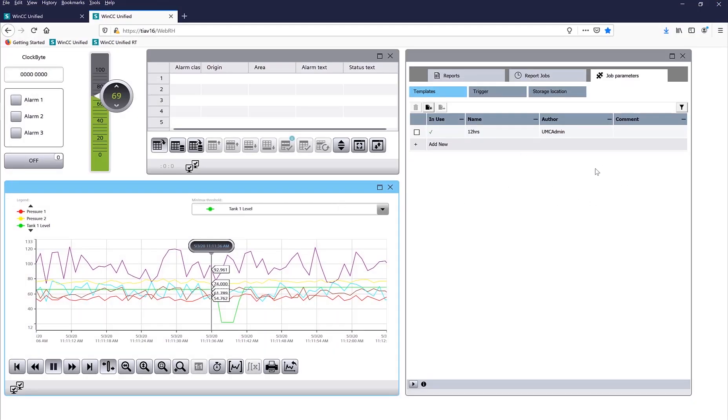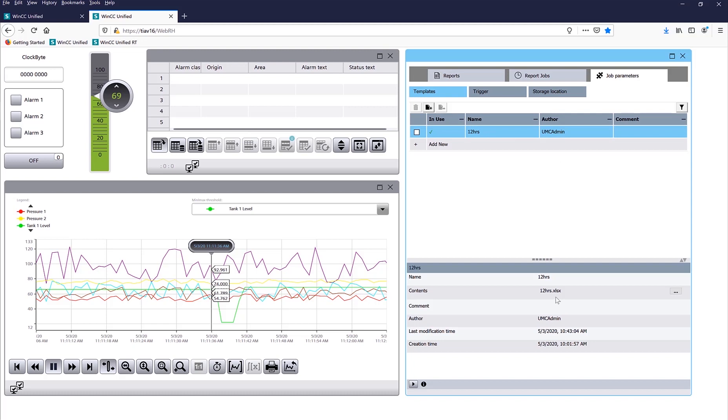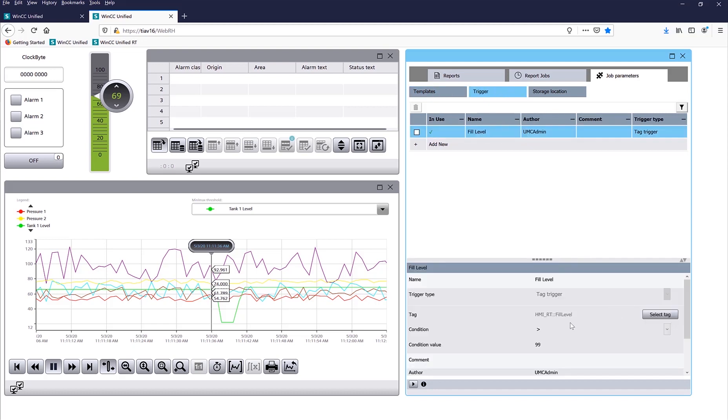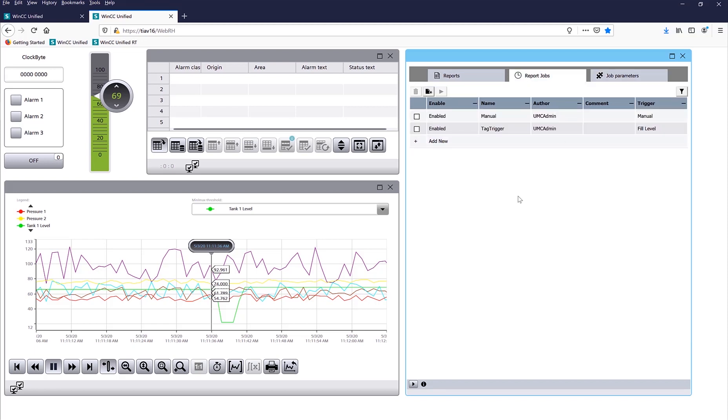Here is some nice report objects, so here is my job parameters. What templates, I'm using a template called 12Hours.Excel, so it's an Excel plugin. I'll show you in a minute how I created that template, we'll create a new one. Here is a trigger, so if my fill level goes higher than 99, I want to trigger a report.